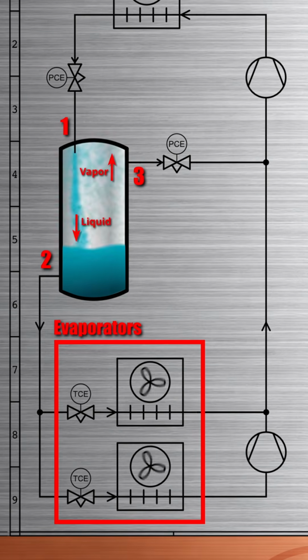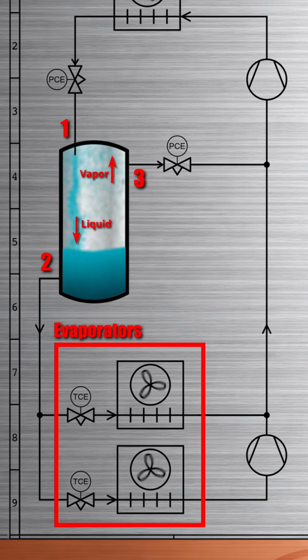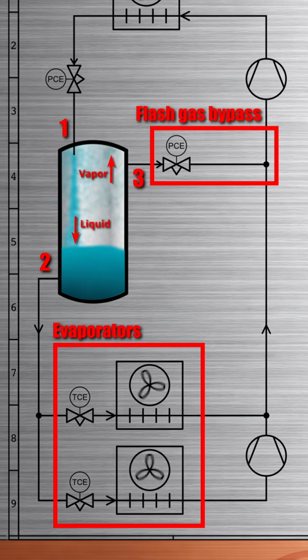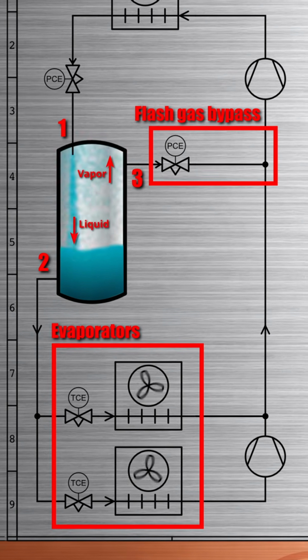And the third port is used to reduce the vapor inside the receiver. It's called flash gas bypass, or for short, the gas bypass. So these are the first three ports of the receiver. But wait, there's more!